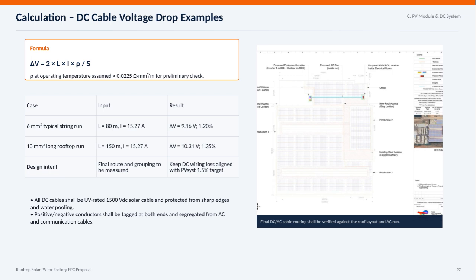For a longer 10 millimeters squared rooftop run of 150 meters with the same current, the drop increases slightly to 10.31 volts, or 1.35%. Our design intent is to confirm the final cable routes and groupings to keep the DC wiring loss in line with the PVsyst target of 1.5%. It's important to note that all DC cables must be UV rated for 1500 volts DC and protected from sharp edges and water pooling to ensure durability. Additionally, positive and negative conductors should be clearly tagged at both ends and kept separate from AC and communication cables. Lastly, the final DC and AC cable routing will be verified thoroughly against the roof layout and AC run to ensure compliance and efficiency.